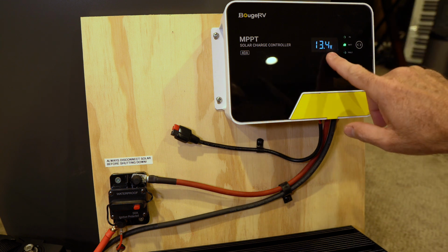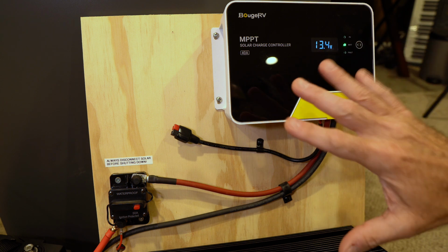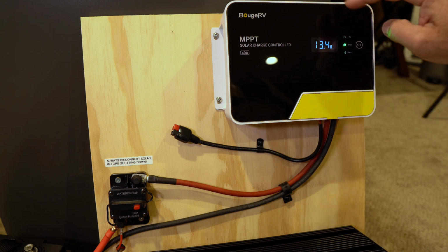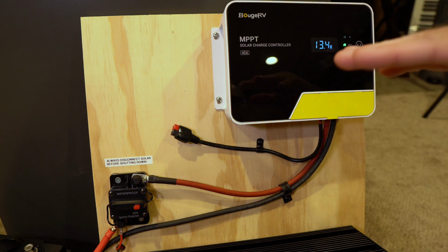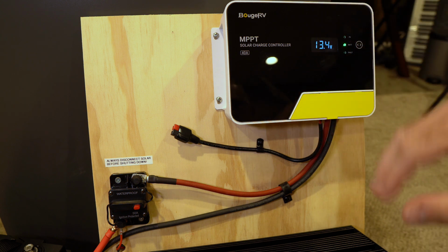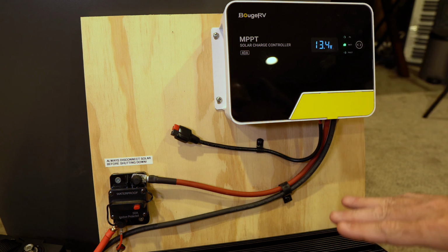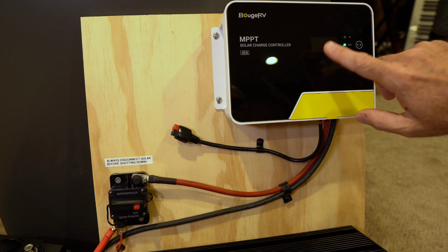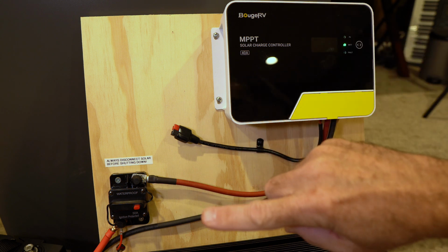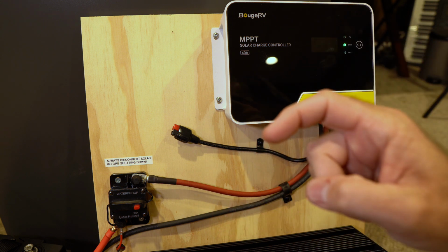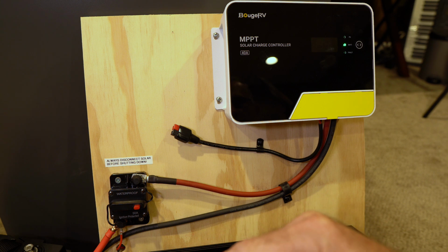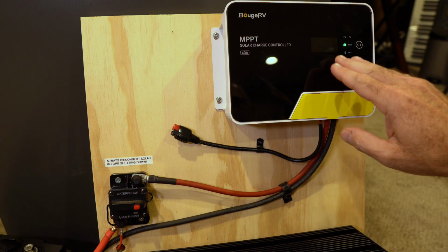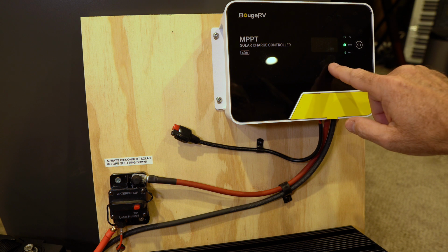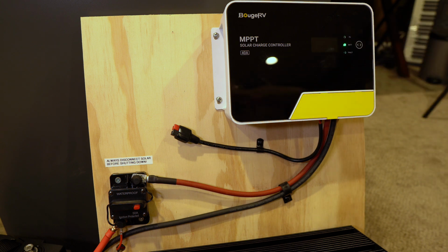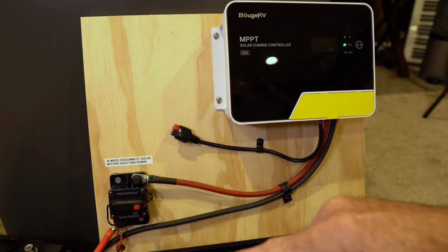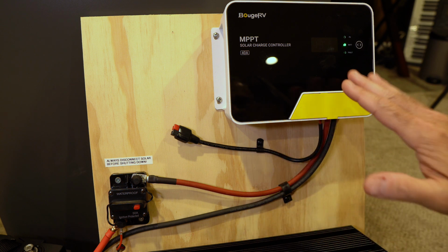One area where you might want to keep this differential in mind is when setting your low voltage disconnect, where I don't want to run the battery past, say, 11 volts. When this says 11 volts, I'm probably actually reading 10.9 volts on the battery with a multimeter. So I might want to set this to 11.1 volts so that it disconnects at that actual 11 volt reading from the battery. Hopefully that made sense, but I just wanted to point that out.